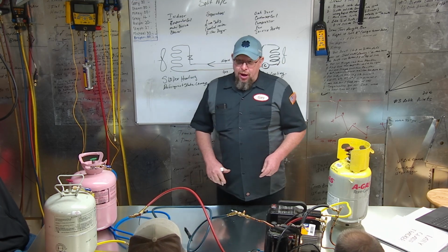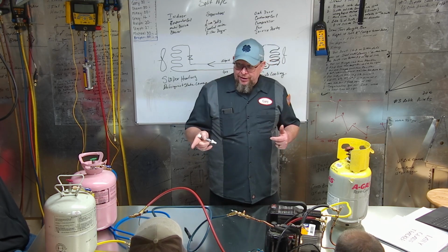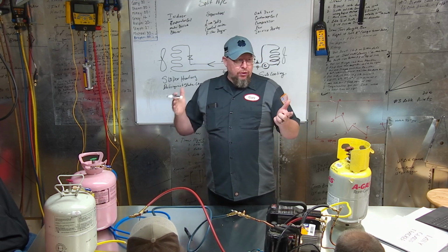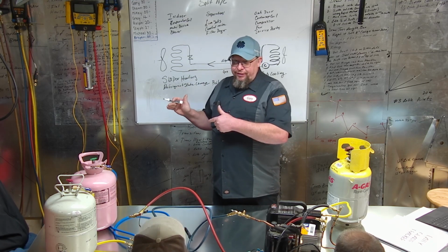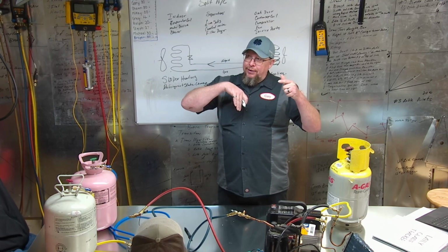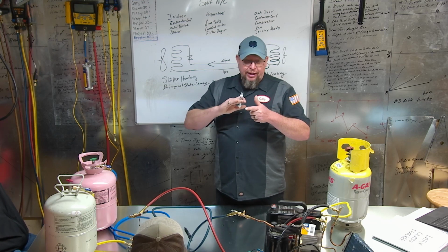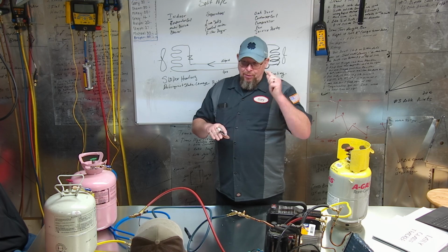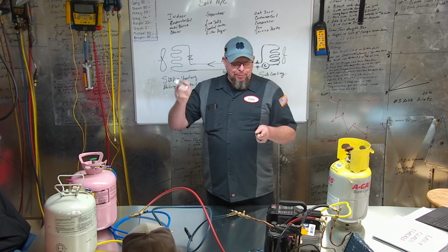So, what temperature are we trying to keep the evaporator coil, Greg? Yeah, 40 degrees. We're really trying to keep a delta T of about 20 degrees. So if it's 70 degrees coming across it, we want our return to be 20 degrees hotter than our supply.